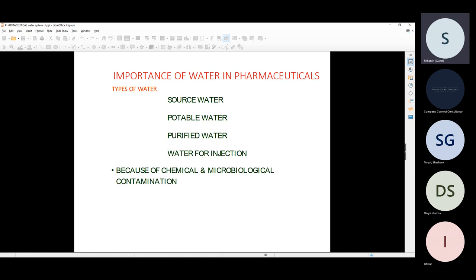If you want to call it purified water, the conductivity should be less than 1.3 microsiemens per centimeter, TOC should be 500 ppb, and pH should be 5 to 7. Coming to the microbial load, the unit for microbial contamination is CFU per ml, colony forming unit per ml. Our limit is 100 CFU per ml, so our purified water should be less than 100 CFU per ml. QC persons will take the sample, analyze it, and give the records.